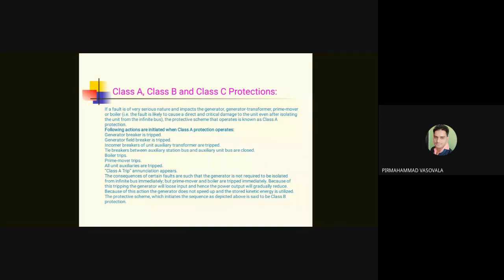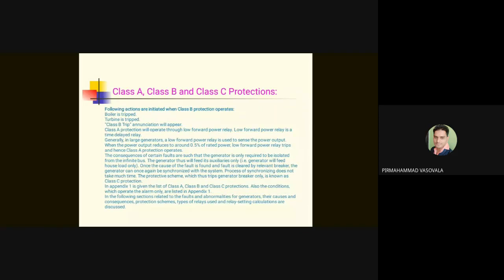Class B, we make use of the kinetic energy of the generator. That is, we don't trip everything. As you can see on the screen, in case of class B trip, the boiler is tripped and the turbine is tripped. That means we trip the boiler, that is, all flames are extinguished, and the steam stop valve is closed. Therefore, the turbine will not run. Then what will happen? The mechanical energy from the turbine is not available to the generator.